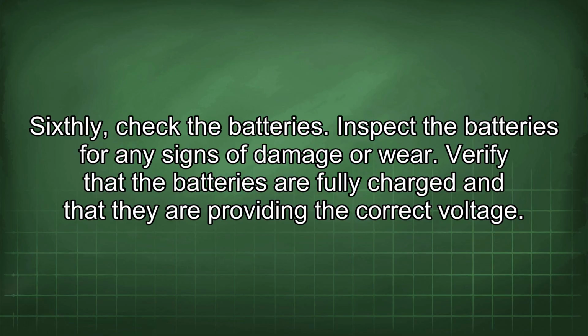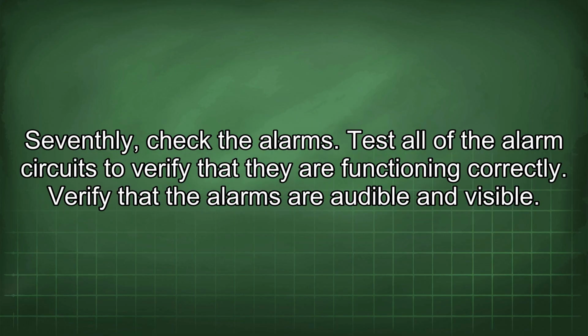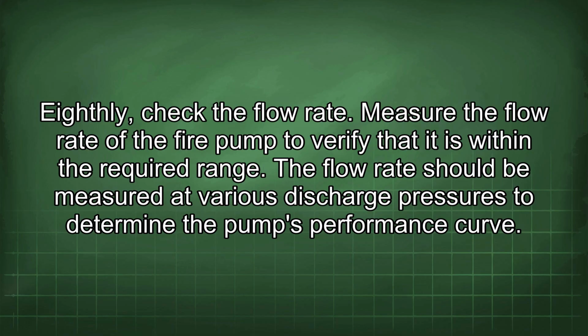Sixthly, check the batteries. Inspect the batteries for any signs of damage or wear. Verify that the batteries are fully charged and that they are providing the correct voltage. Seventhly, check the alarms. Test all of the alarm circuits to verify that they are functioning correctly. Verify that the alarms are audible and visible. Eighthly, check the flow rate. Measure the flow rate of the fire pump to verify that it is within the required range. The flow rate should be measured at various discharge pressures to determine the pump's performance curve.